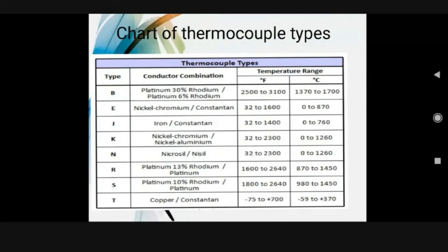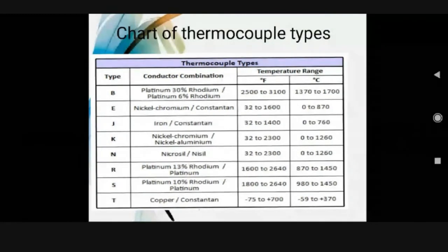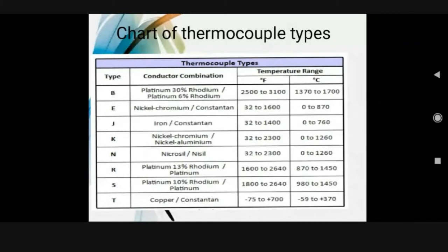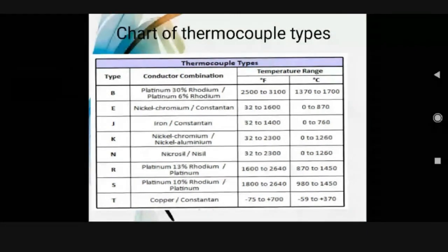Platinum 30% rhodium, platinum 6% rhodium, 2500 to 3100 Fahrenheit, and 1370 to 1700 degrees Celsius. Type E, nickel chromium constantan, 32 to 1600 Fahrenheit, 0 to 870 degrees Celsius.